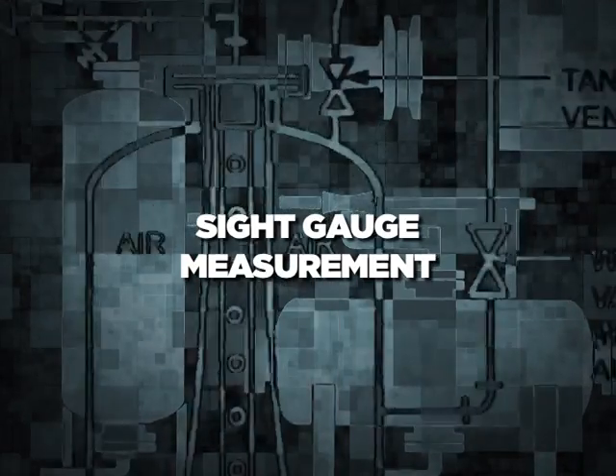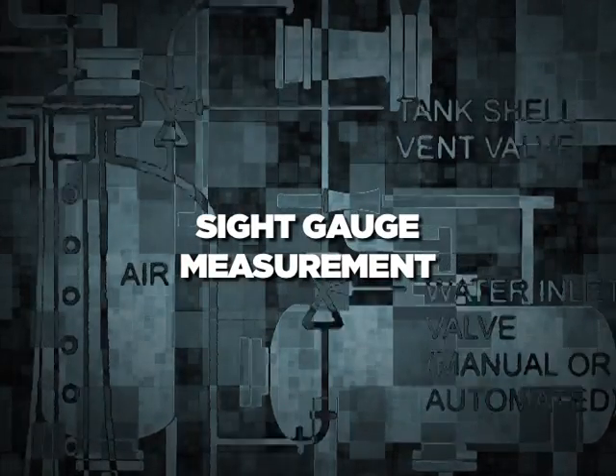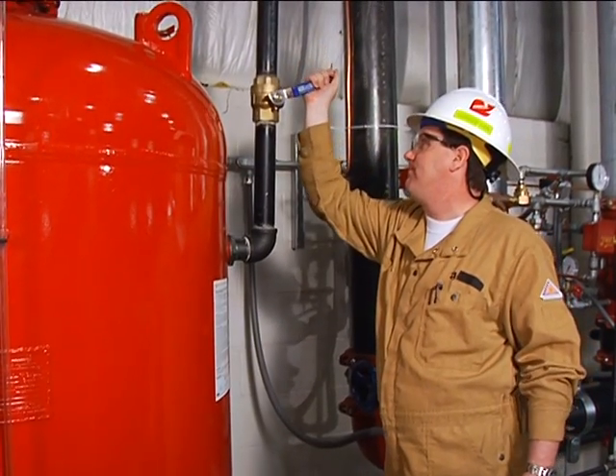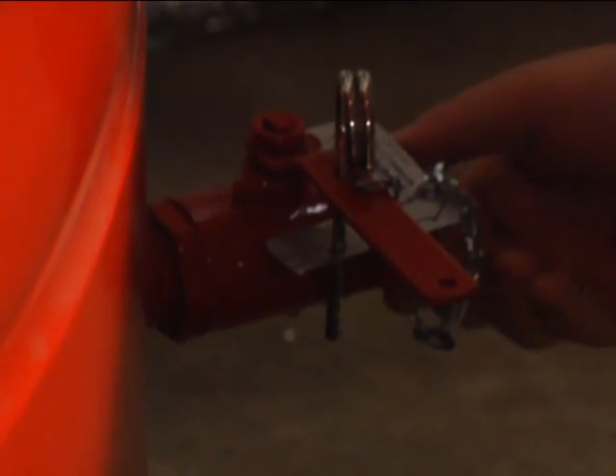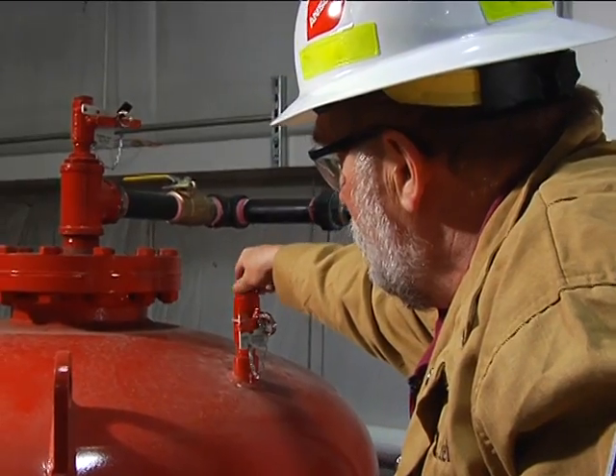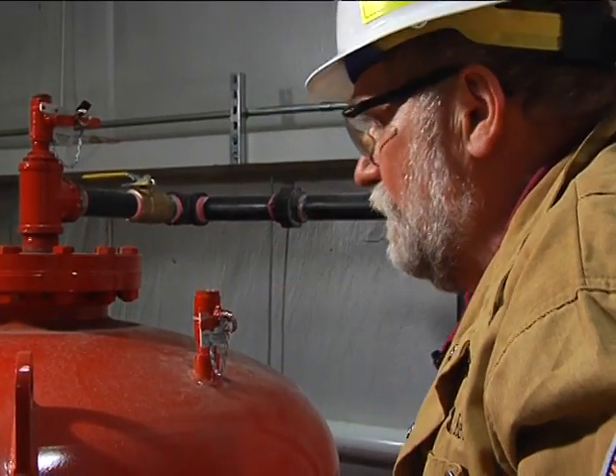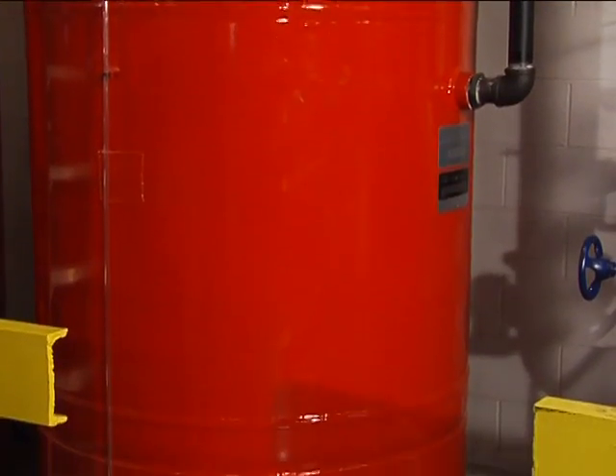Foam concentrate measurement procedures. Sight gauge measurement. First, you need to close the water inlet valve. The next step is to open the tank shell drain valve and tank shell vent valve until all of the water is drained and all pressure is relieved from the tank.